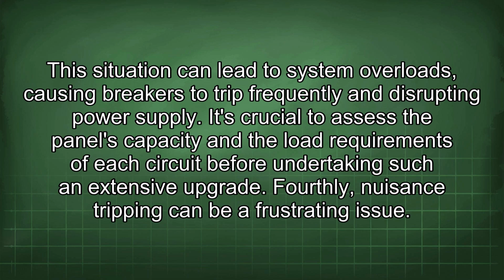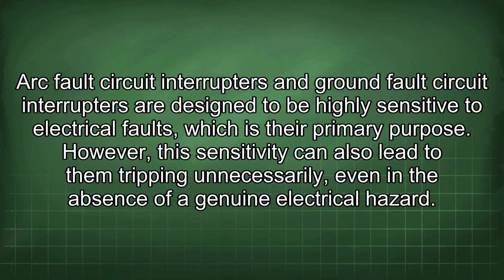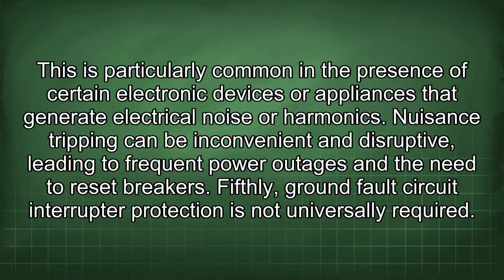Fourthly, nuisance tripping can be a frustrating issue. Arc fault circuit interrupters and ground fault circuit interrupters are designed to be highly sensitive to electrical faults, which is their primary purpose. However, this sensitivity can also lead to them tripping unnecessarily, even in absence of a genuine electrical hazard. This is particularly common in the presence of certain electronic devices or appliances that generate electrical noise or harmonics. Nuisance tripping can be inconvenient and disruptive, leading to frequent power outages and the need to reset breakers.